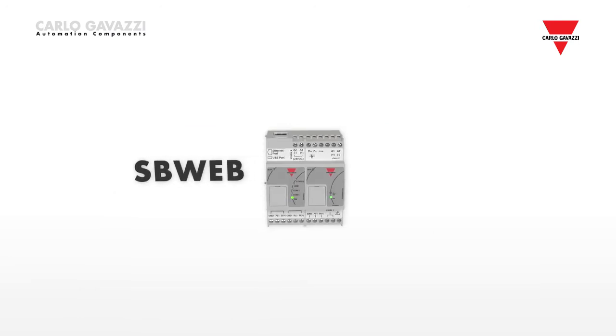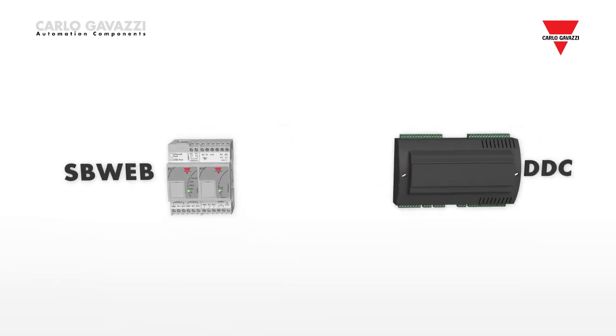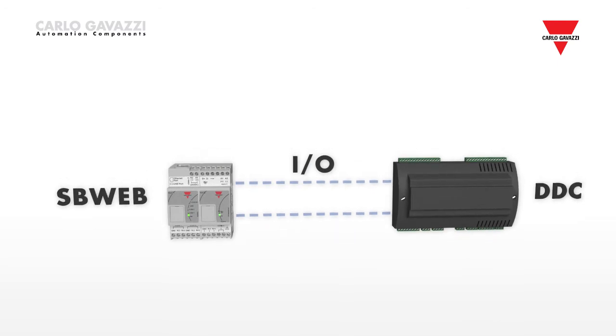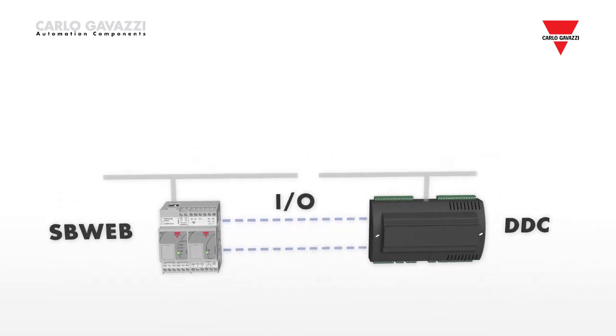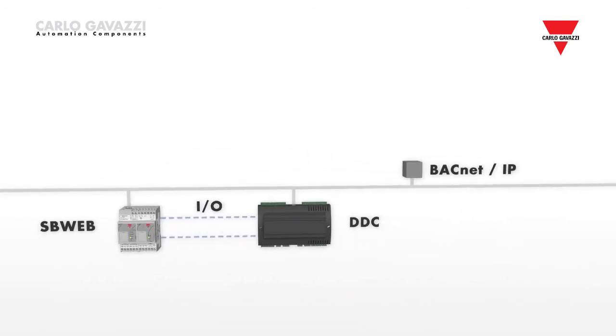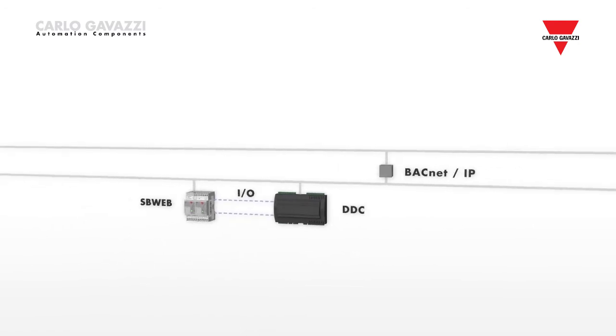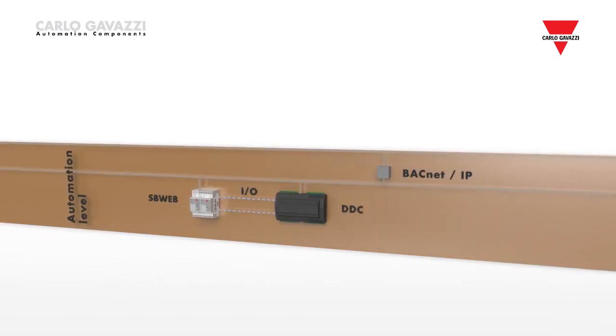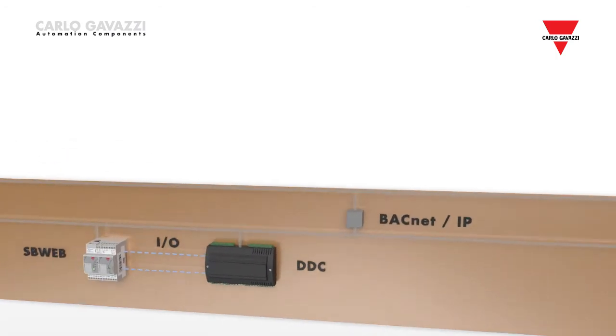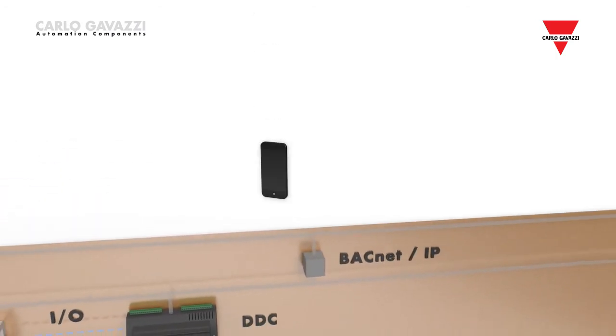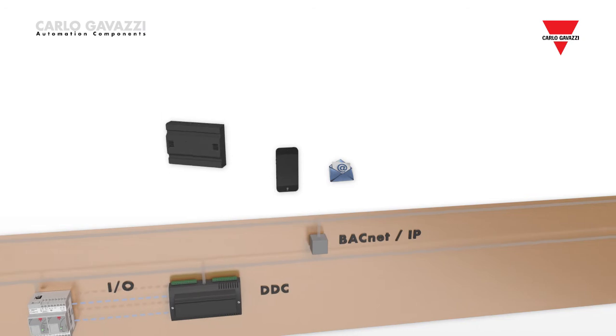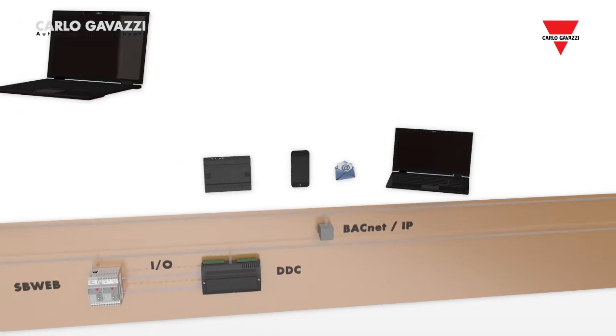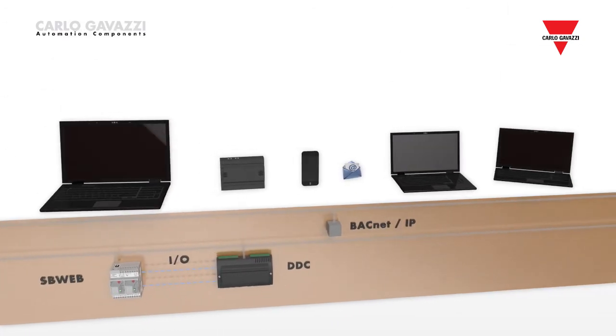Thanks to the BTL-certified BACnet controller SB Web, system integrators can easily integrate Dupline with their existing building management system, regardless of brand. HVAC management takes place in the DDC controller just as before. Dupline is simply used as remote input-output. Each data point is transformed into a BACnet object, ready to be used by any DDC controller on the BACnet IP network.